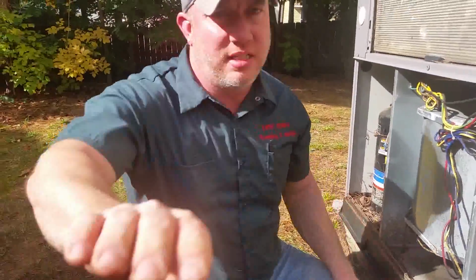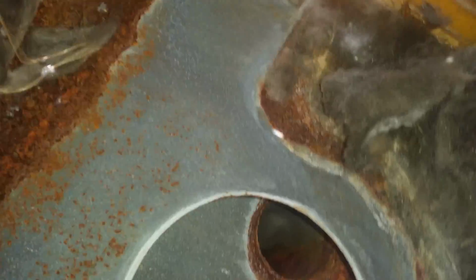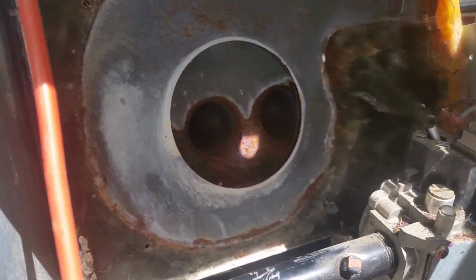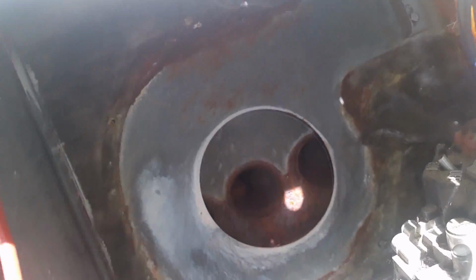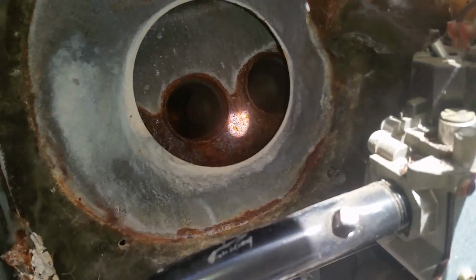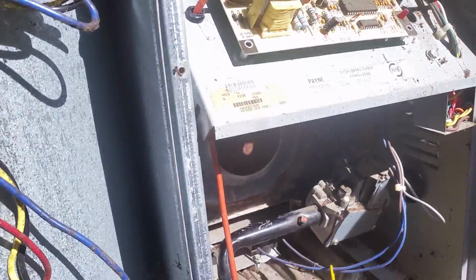One of the things that you want to do is check your back plate. This plate here, this one's in very good shape, but if you're completely rusted out through here, then you're going to want to replace, this is what we call the back plate, or the firewall plate. And you're also going to want to check the heat exchanger, because what's the point of putting on a draft inducer on a unit with a bad heat exchanger? Now this one here, you can see the heat exchanger is pretty rusty on the inside, but we're going to check on the outside for cracks and holes. So we'll show you that in a second.